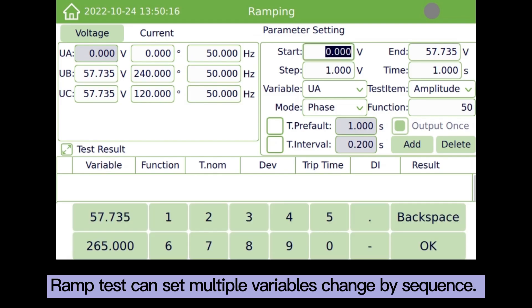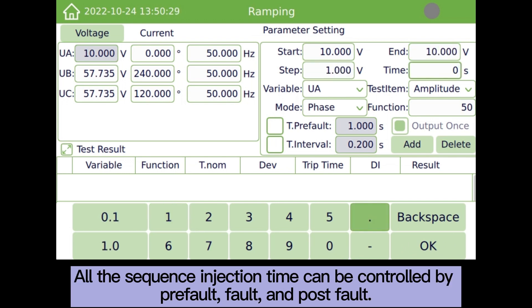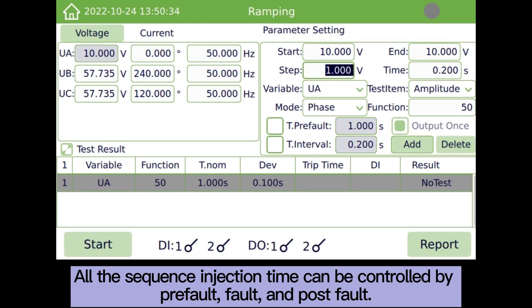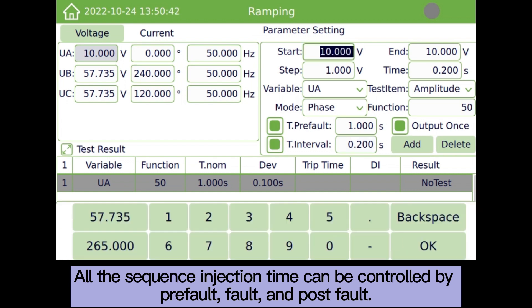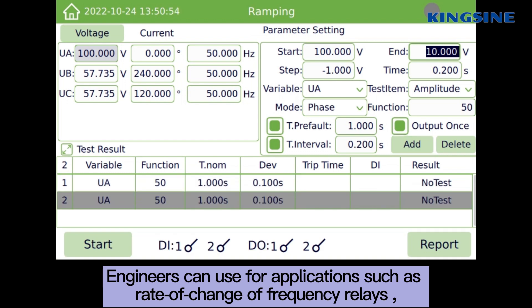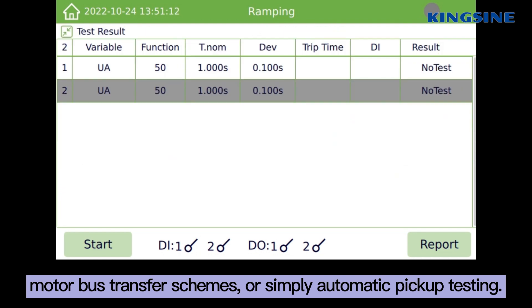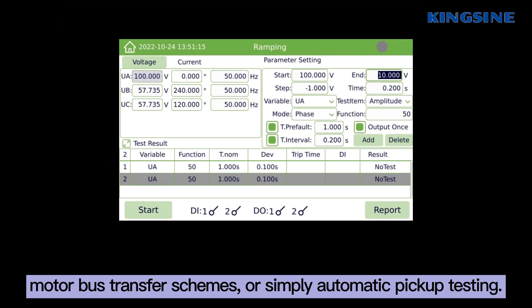The ramp test can set multiple variables to change by sequence. All sequence injection times can be controlled by pre-fault, fault, and post-fault. Engineers can use for applications such as rate of change of frequency relays, motor bus transfer schemes, or simply automatic pickup testing.